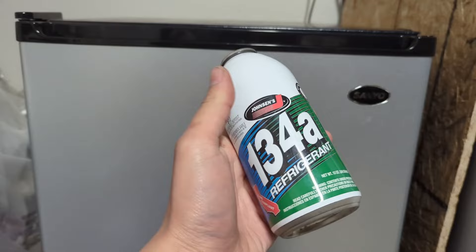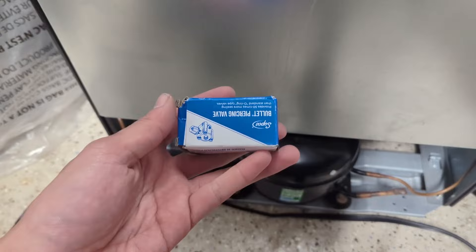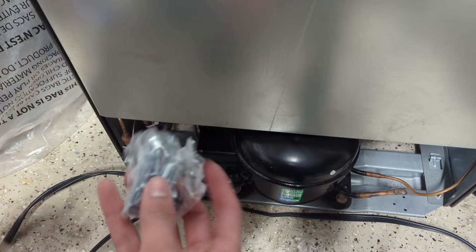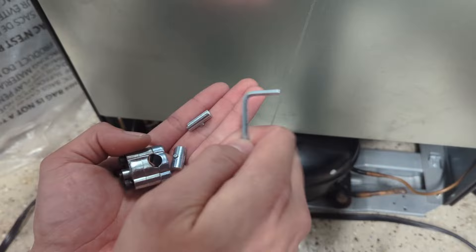Now comes the star of the show, the Supco Bullet Piercing Valve. This costs about $5. I'll have a link to buy one in the description, and it comes with everything you need to tap into your refrigerator. It comes with the valve itself, a hex key for tightening, and two inserts. We're going to be using the smallest of the inserts, which is for quarter inch tubing, because this mini fridge is built using quarter inch tubing.